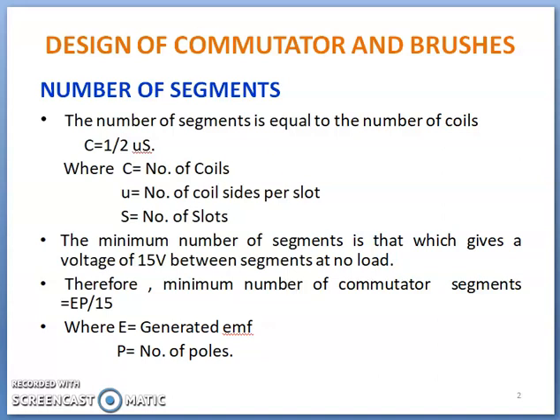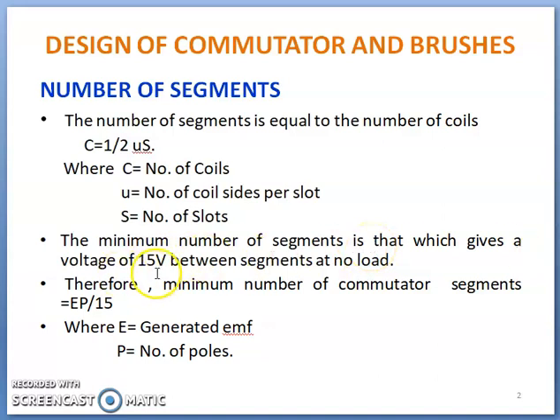Under the design of commutator, the number of commutator segments is decided as follows: the number of commutator segments is equal to the number of coils, given mathematically as C = half · U · S, where C is number of coils, U is number of coil sides per slot, and S is number of slots. The minimum number of segments is that which gives a voltage of 15 volts between segments at no load.